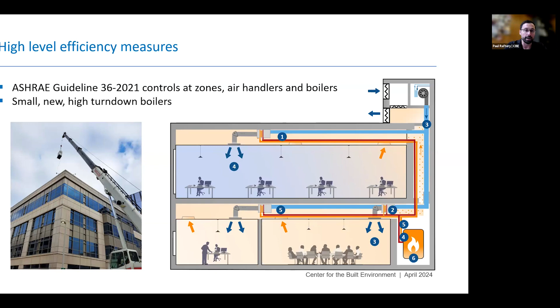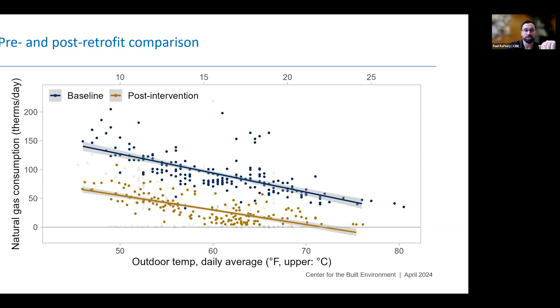Here you're seeing on the y-axis the daily gas consumption, from the utility bill from PG&E. On the x-axis, we're seeing the daily average outdoor temperature. The blue line is pre-retrofit and the yellow line is post-retrofit. As you can see, there's a huge step change in energy consumption in these buildings.